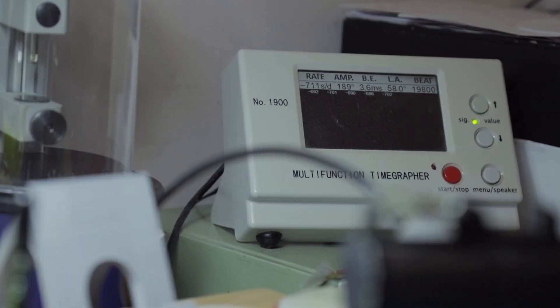So just quickly double checking and making sure that's settling back, it's not quite hitting the 180 degree marker and it's sort of landing in between 90 and 180, about 135, 140 degrees. Now if we look at the time grapher and we take a look at the time grapher trace, you can see the readings on there. We're getting a reading currently of about 205 degrees.